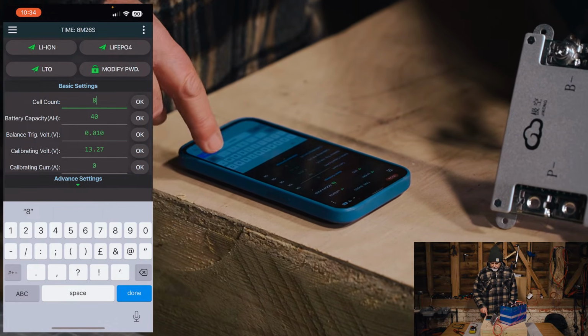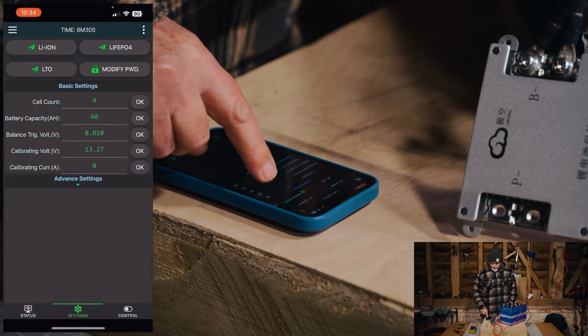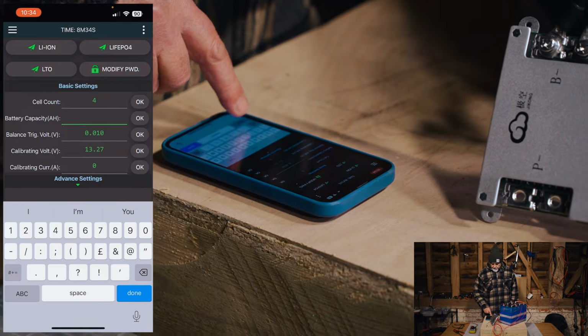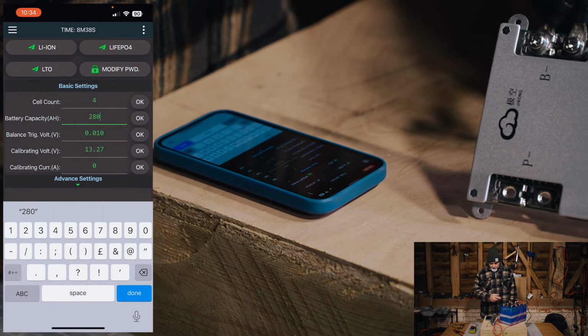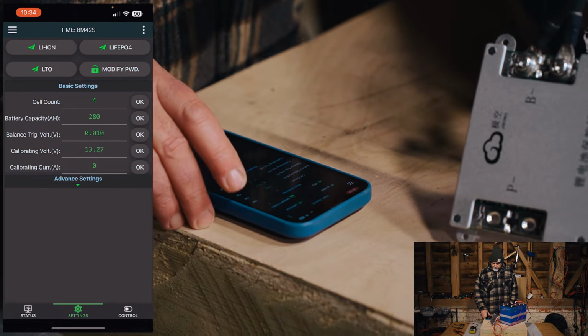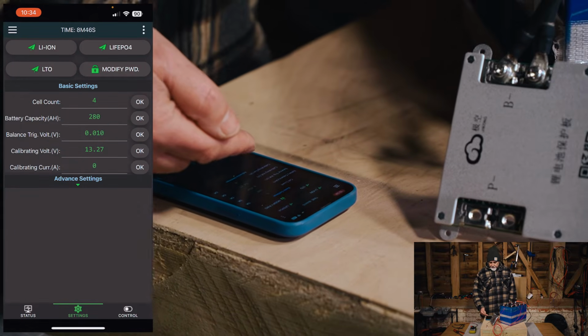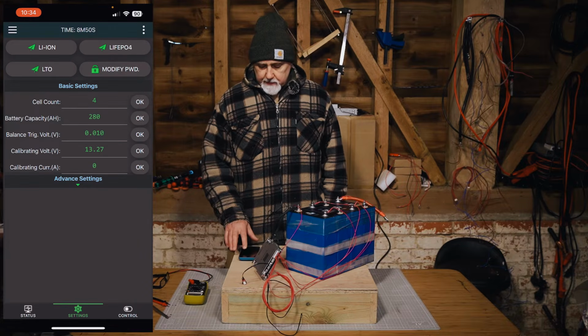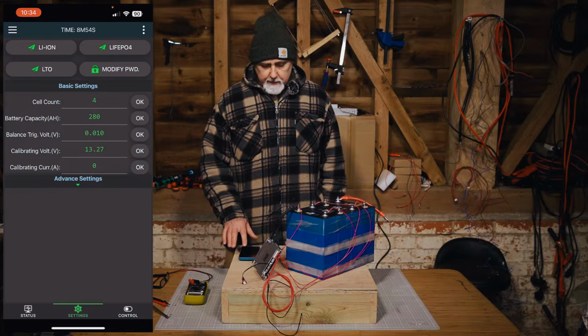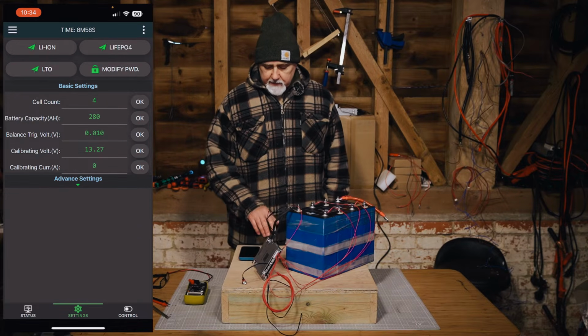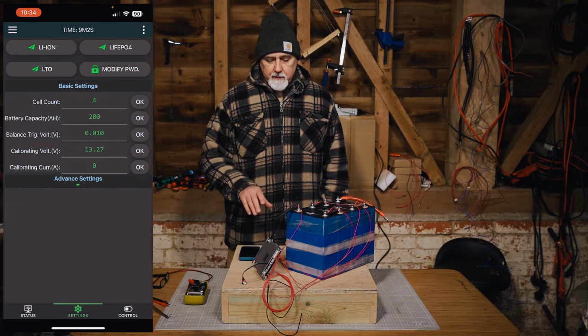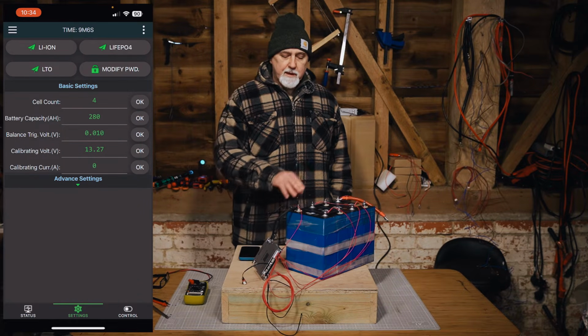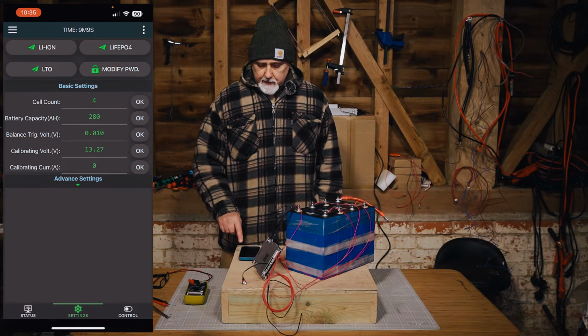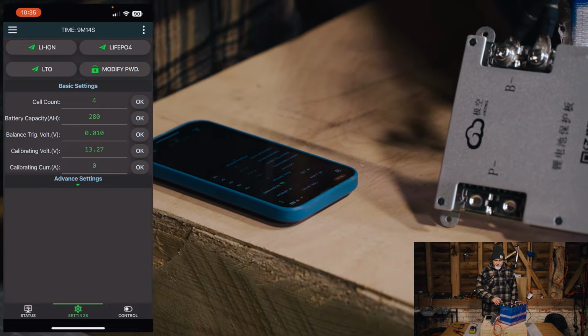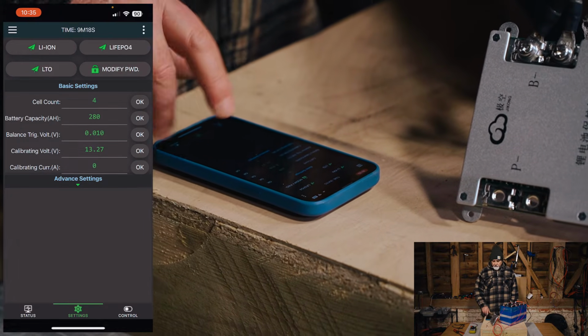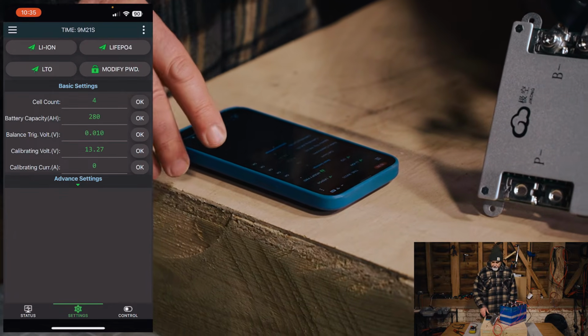So let's go to the cell count, and let's change that to 4. We click OK. These are, I think, 280 amp hour cells. I can't actually remember, but they're just cheap demo cells. They're not our usual ones. Okay. So we've told it how many cells we have, and the capacity. Now, the balance trigger voltage is a bit of a misleading description, but basically when the delta exceeds this value, balancing will start. The delta is the difference in voltage between the highest voltage cell and the lowest voltage cell. So when that delta exceeds 0.01 volts, it will start balancing and bring them back up to the exact same level.